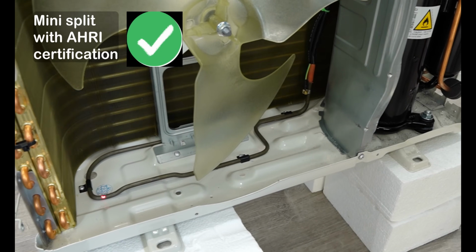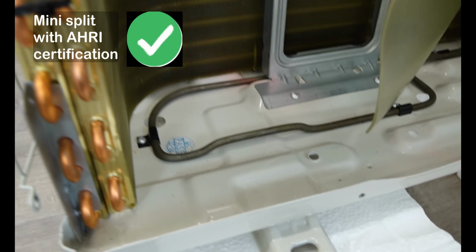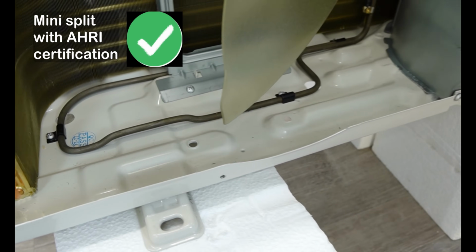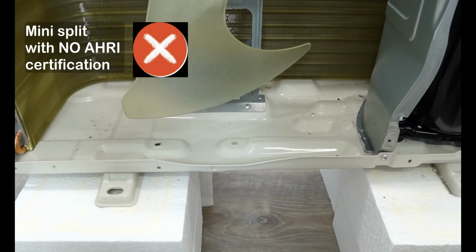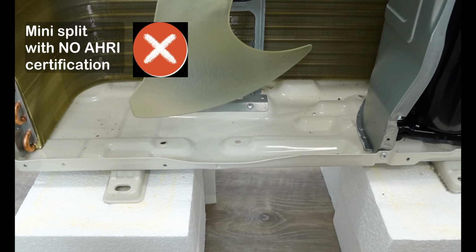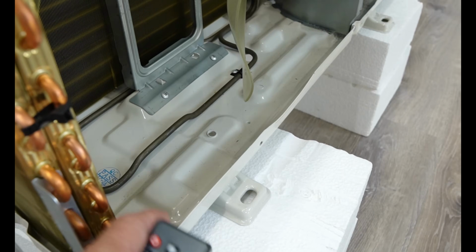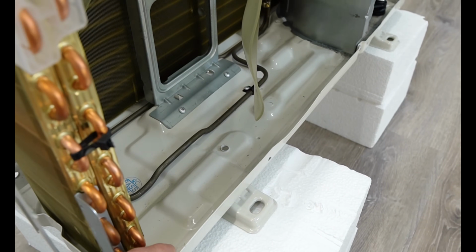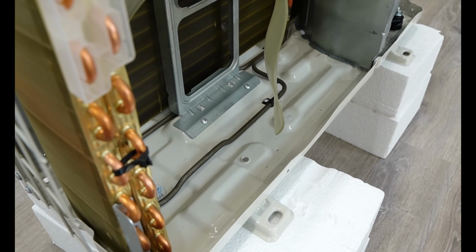This unit also has a bottom plate heater, while the other does not. Yeah, the heater is absolutely critical. Without it, the ice can potentially destroy the fan blade. For a side discharge unit, I always prefer to have a bottom plate heater. Without that, I guess that's a deal killer to me.